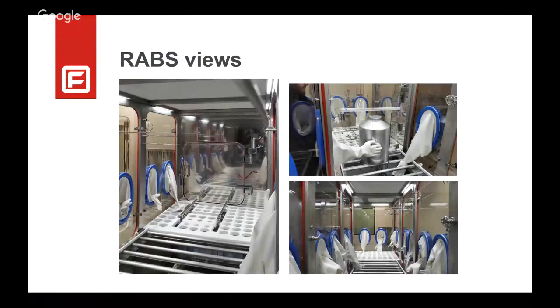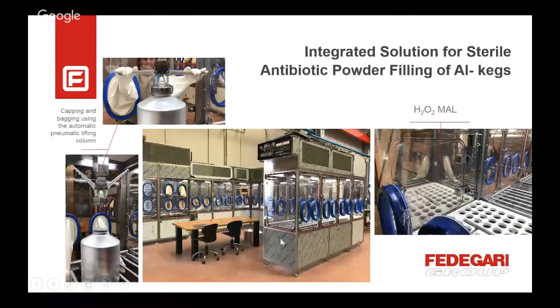Here we have some nice views of the system. This is the door of the material lock, the opening. In this case, it's closed. What is important to say is that we have developed a gasket system, an inflatable gasket, to be sure that no leaks of hydrogen peroxide happen during the process outside the chamber. And the dosing area of the RABS is separated by doors to be sure that no powder goes into the other part of the RABS. These photos were taken in our factory acceptance test bay area.